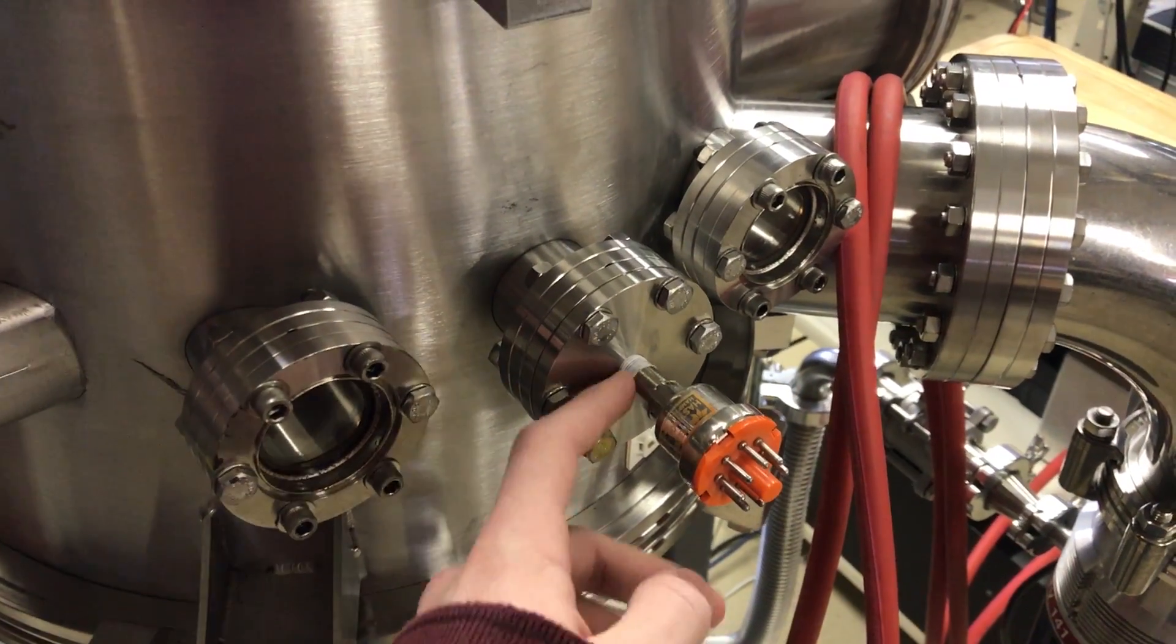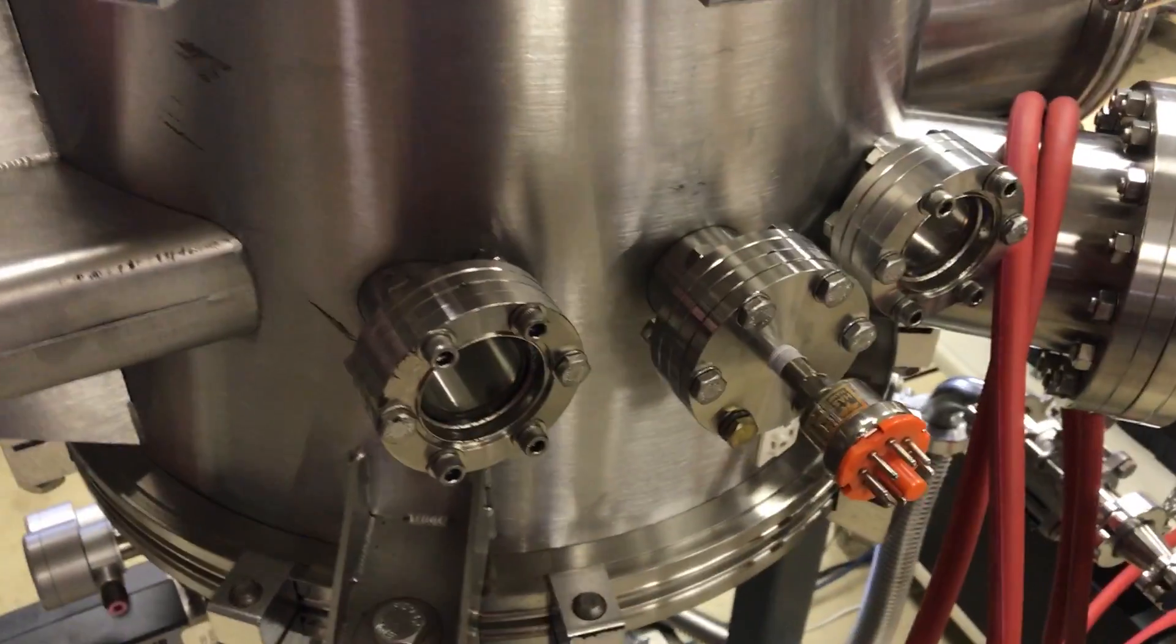NPT is not the best for high vacuum, but I mean, it's all right. As long as you use Teflon tape and have a thermocouple gauge on there. But that conflat size is quite common to see.